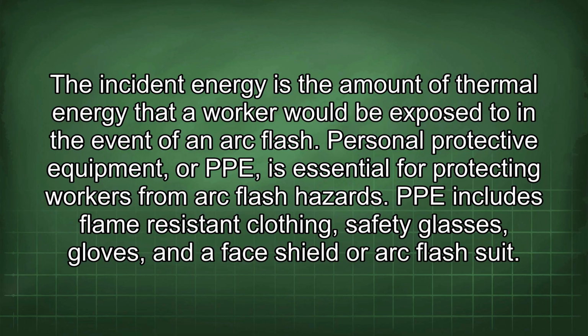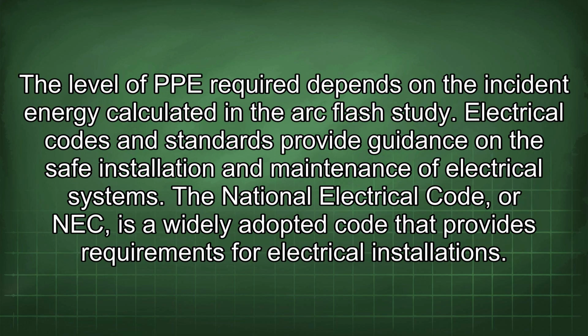Personal protective equipment, or PPE, is essential for protecting workers from arc flash hazards. PPE includes flame-resistant clothing, safety glasses, gloves, and a face shield or arc flash suit. The level of PPE required depends on the incident energy calculated in the arc flash study. Electrical codes and standards provide guidance on the safe installation and maintenance of electrical systems.